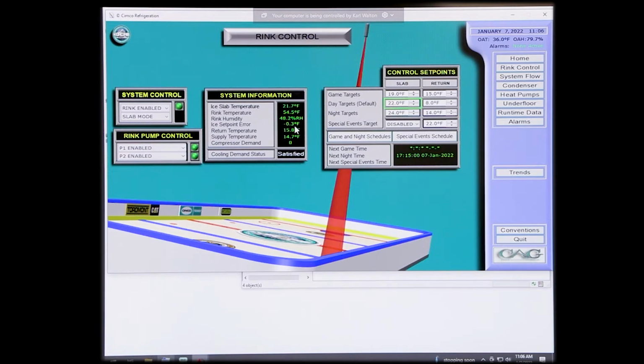Your ice error, okay. Ice error is, we control on slab mode, half a degree above, half a degree below. So we currently have a set point of 22. When we reach 22.5 degrees slab temperature, we will start the system based on how many compressors we choose through other things that we're going to go over here, how much lag time before the next compressor starts, or compressor demand limit. If we only choose to run 2 machines, then we can have that in play as well, whether we run 1, 2, or 3 machines. So we control at 22.5.